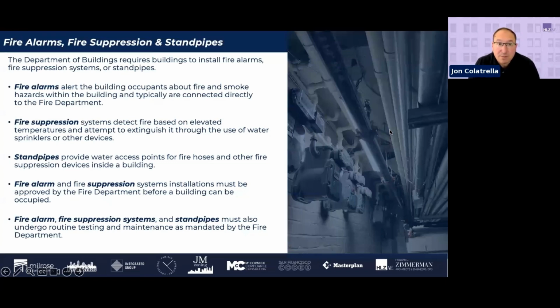Fire suppression, typically a sprinkler system, falls under your fire suppression items. And this is a system that is heat-based, detects a fire based on elevated temperatures, and attempts to extinguish that fire or at least contain the fire while the FDNY is en route. From the engineering side, the design criteria, which many don't know, is 30 minutes of sprinkler coverage in the most remote zone. This is giving that critical window to the FDNY to get to the building within 30 minutes before that sprinkler system is, per se, out of water, depending on what it's connected to. Switching over to standpipes. Standpipes are a little bit different. There are combination sprinkler and standpipe systems, but a true standpipe system provides access points for water to the FDNY, typically run up and down the egress stairs of a building, and it allows hoses to be connected.